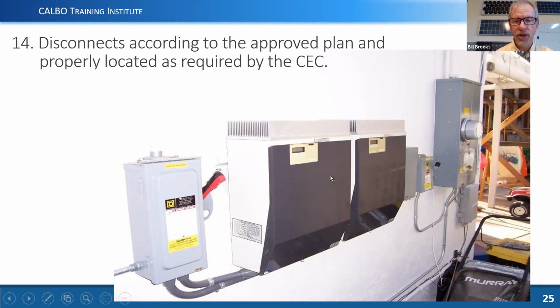In this particular case, we're showing a situation where they combined the two inverters in a box. And back in the day, way back in the day, we were required to have visible break switches. There still are some communities out there in California that require those. Most do not. And so the circuit breakers that are in here would be acceptable. Or since this is actually inside of the equipment, a circuit breaker in here would be an acceptable way to disconnect the AC side of the system. And of course, on the left here is the DC side.